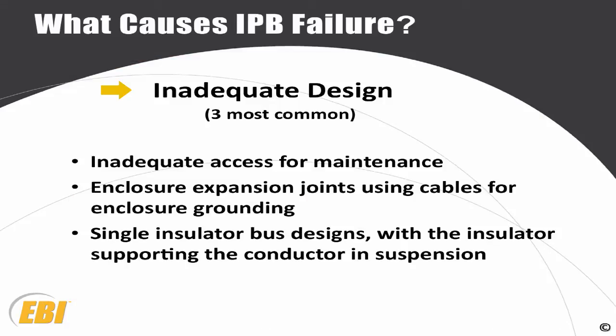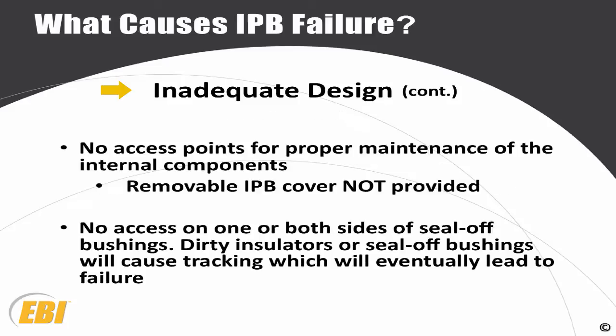Under inadequate design, three of the common things that we see is inadequate access for maintenance. What happens here is the OEMs do not provide places where you can get inside the bus to clean it. They don't give you a removable cover where you need them to get in there. A lot of times you will have no access to where the seal-off bushings are. Or you may have access to one side, but not the other.